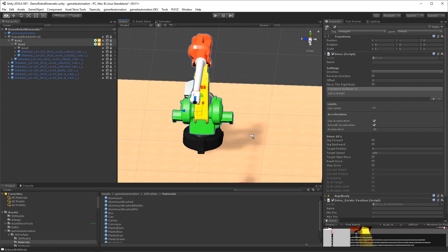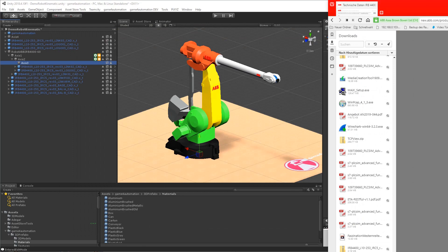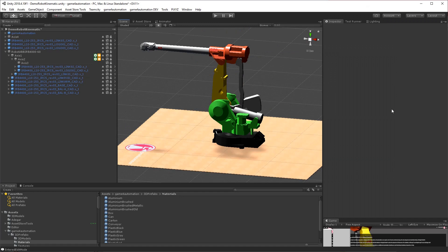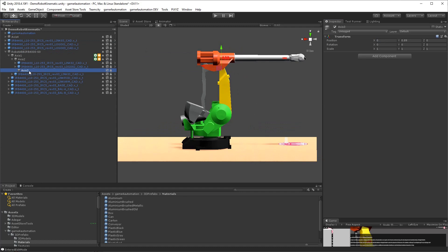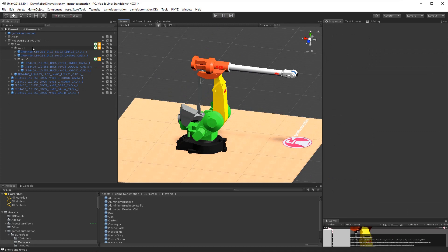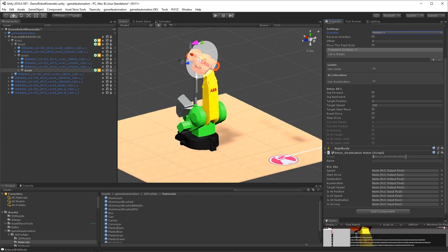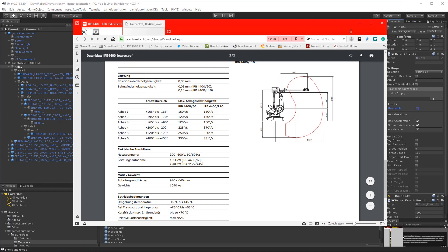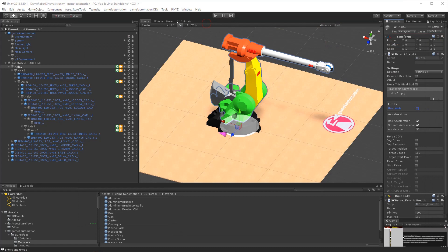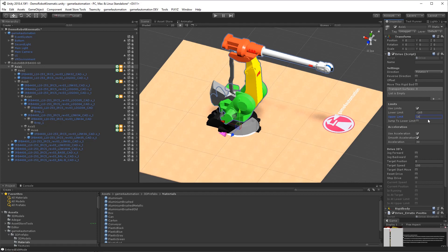We now need to do that with all six axes. As mentioned before, it is better to work with empty game objects because without doing that you will continuously displace your included 3D components. I'm fast-forwarding the recording until I've done that for all of the axes. Next, as an optional step, you can set the min and max positions of the axes to the specification values of the robot. This step is optional if you get the positions from a real robot controller for virtual commissioning, since the real robot controller will have the original axis limits.